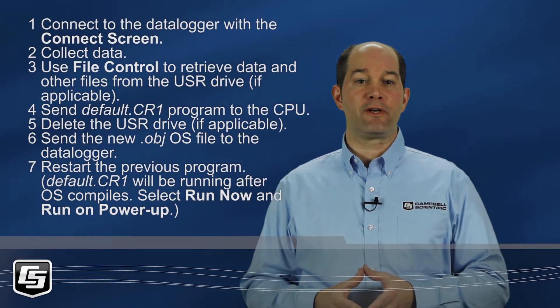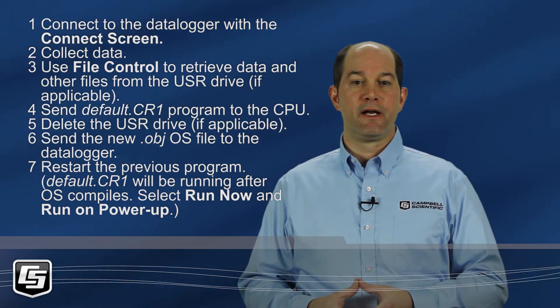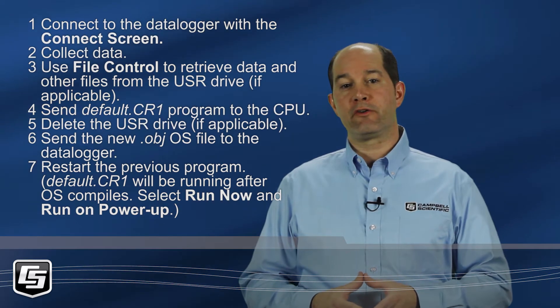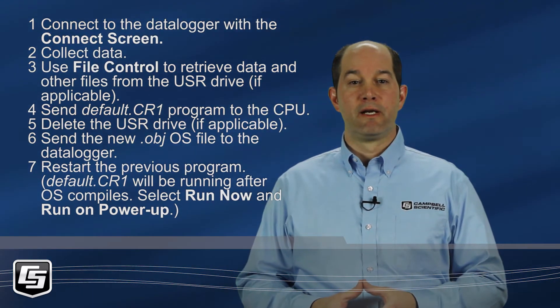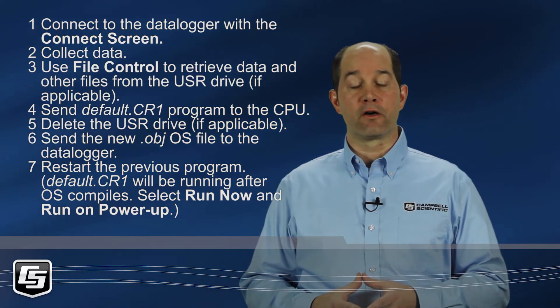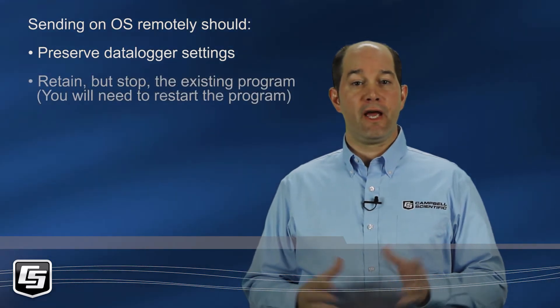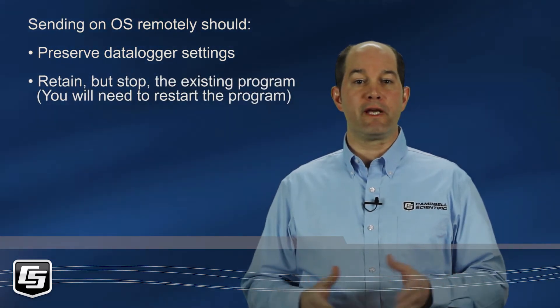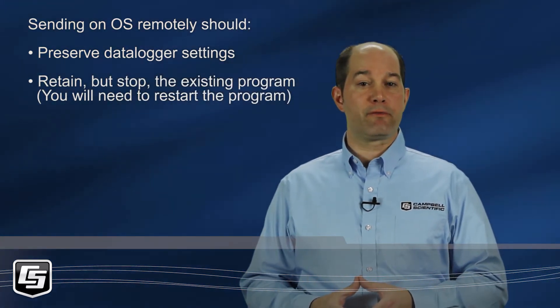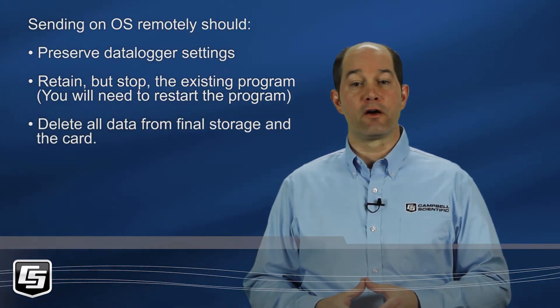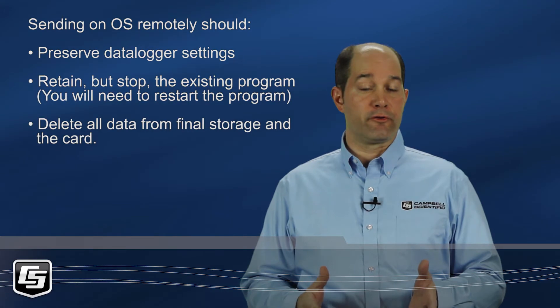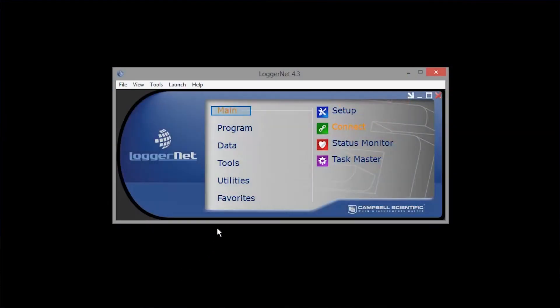For best results, there are some steps you want to take to prepare the data logger. Not every step will apply to your particular installation, nor is every step required every time. But sending an OS to a remote data logger should be approached with caution. Sending an OS using this method should preserve data logger settings, and your program will remain on the data logger but will need to be restarted. All data will be deleted from final storage on the data logger itself and on the card if you're using one.